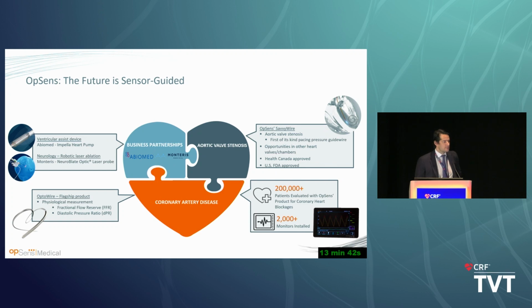Just a few words about OpSens Medical. It's a French-Canadian company, actually, that has been very involved in sensors. Their key product is really an optical sensor, and there are multiple divisions. They are very famous: they are the ones designing the sensor that is in every Impella. Very, very accurate sensor for pressure that can last for more than 90 days in a patient, and the longest Impella has been implanted more than 1 year in a patient, and the sensor is still very robust with no change of signal. So this sensor has been built to last for months. So when you use it to do an FFR for 15 seconds, yes, it's going to be accurate with no drift. They also have a temperature sensor that they use in neurosurgery.